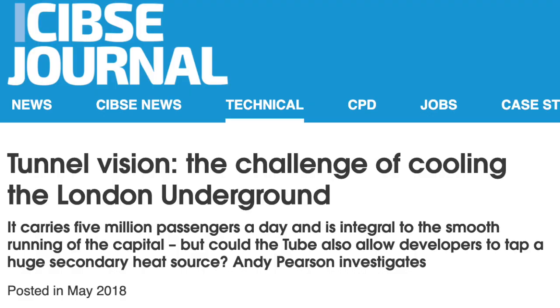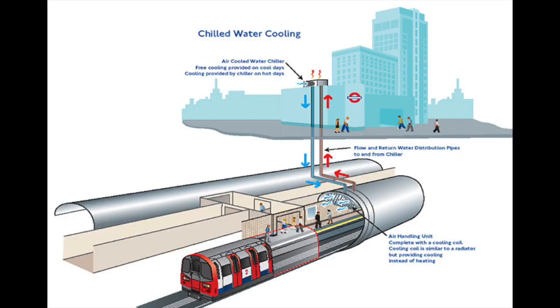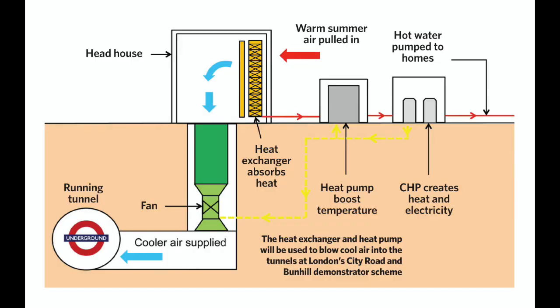She said: Water is extracted at a temperature of about 13 degrees C and passed through two heat exchangers before being re-injected into the ground. The first heat exchanger is used to remove heat from the station's cooling water circuit, which serves above-platform air handling units, raising the temperature of the borehole water from 8 degrees to 21 degrees. There is an opportunity for someone to tap into the second heat exchanger to take this heat out from the borehole water and return it to the aquifer at, say, 6 degrees. End quote.